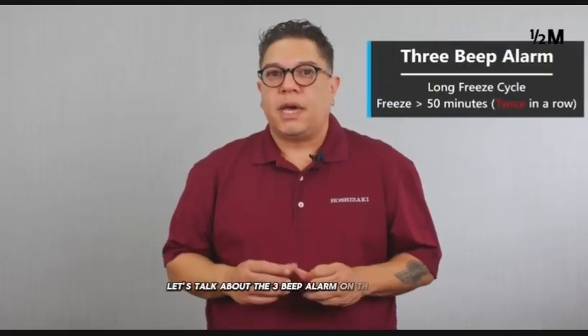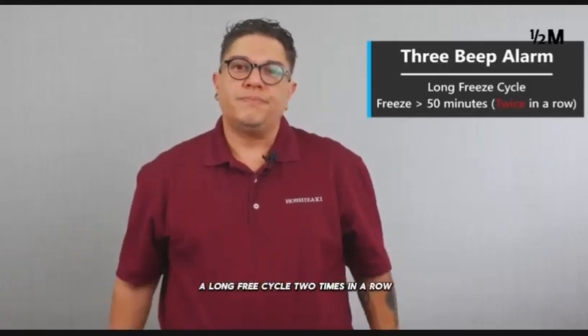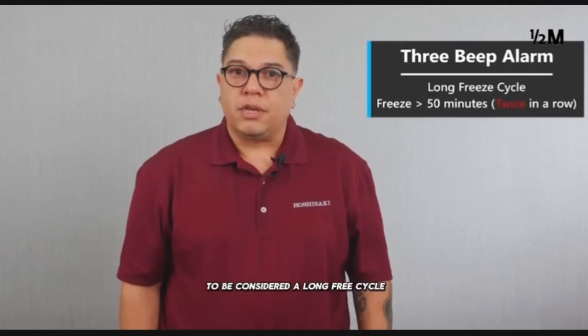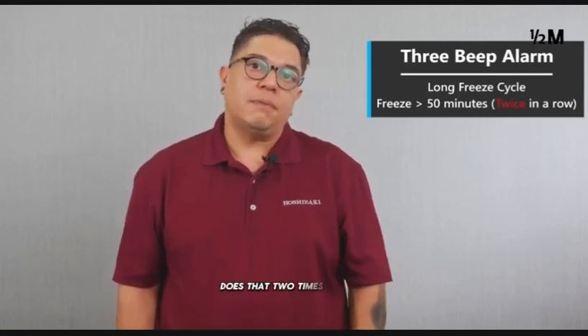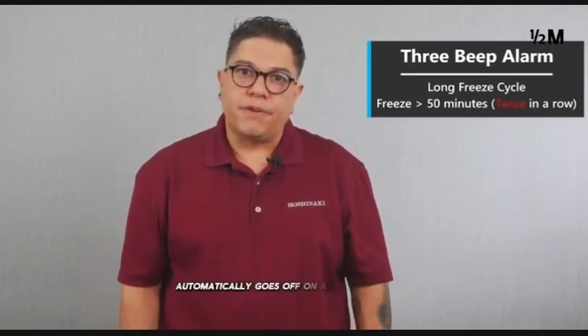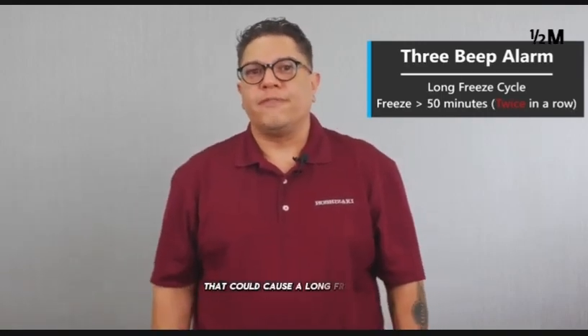Let's talk about the 3-beep alarm on the KM model. The 3-beep alarm means that the machine was running a long freeze cycle 2 times in a row. To be considered a long freeze cycle, the machine has to run about 50 minutes into the freeze cycle. Does that 2 times in a row, it automatically goes off on a 3-beep alarm. We're looking for anything that could cause a long freeze cycle.